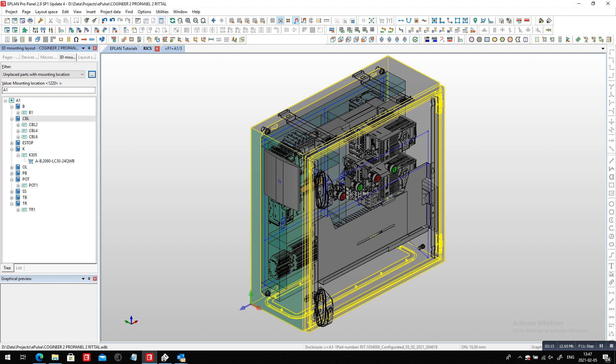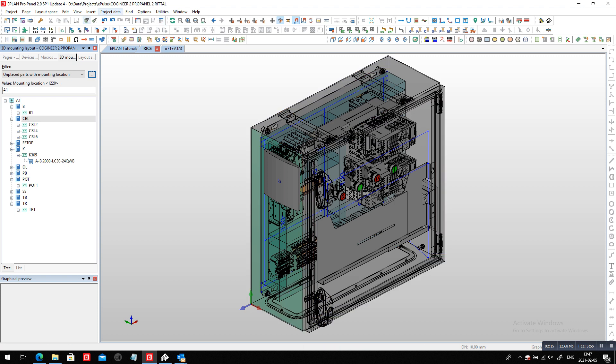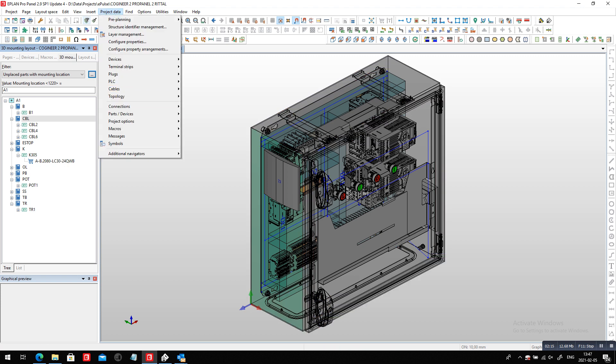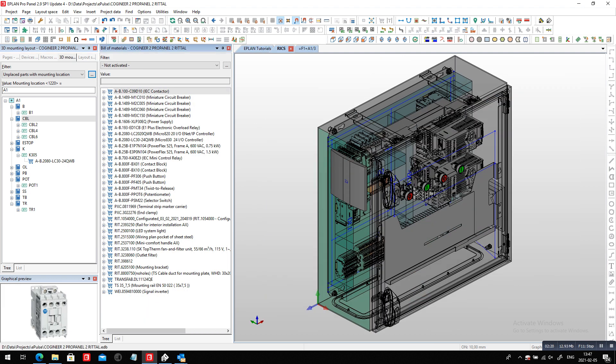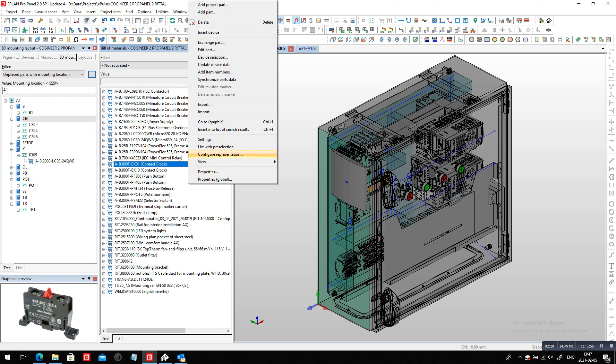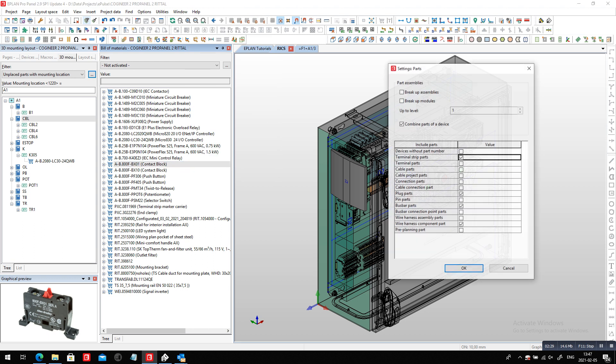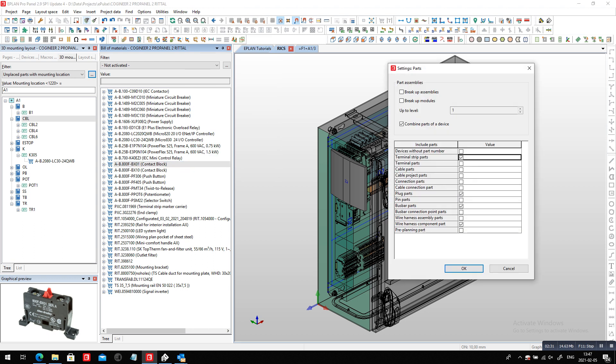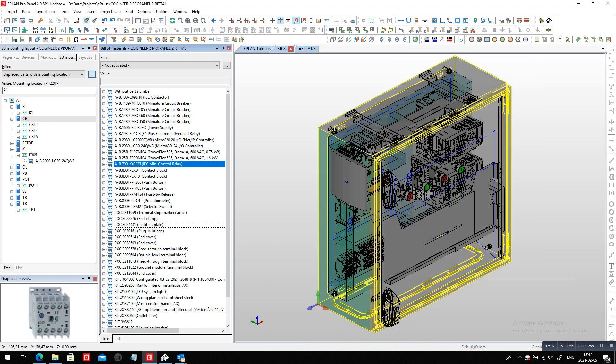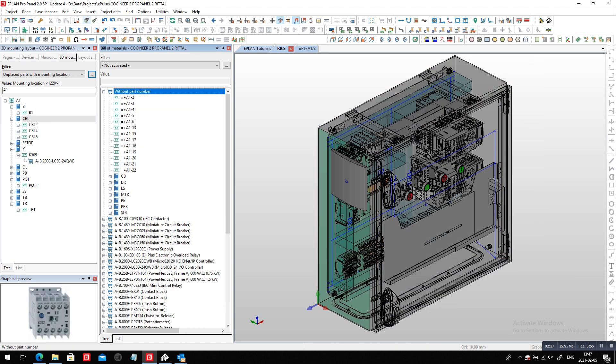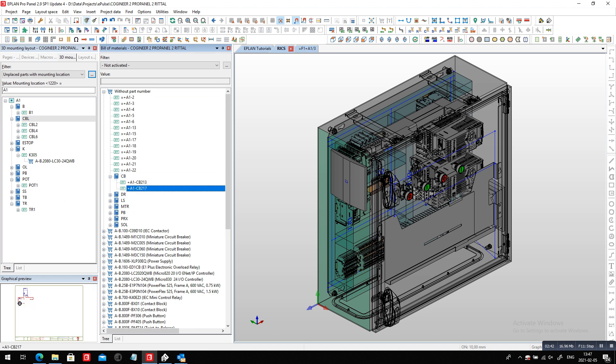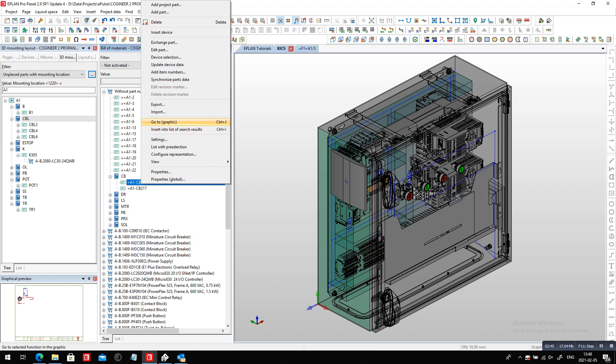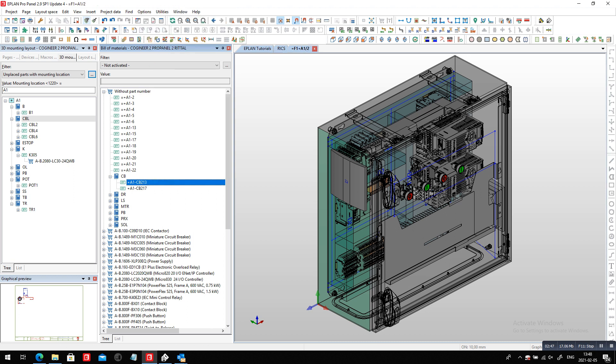But even more important, how do I know that all the devices inside my project and inside this project do have a part number? So when I open here the bill of materials, I can activate a special setting that says, show me all the devices without a part number, any device for terminals. And this pretty much calls up here all the devices that have no part number.